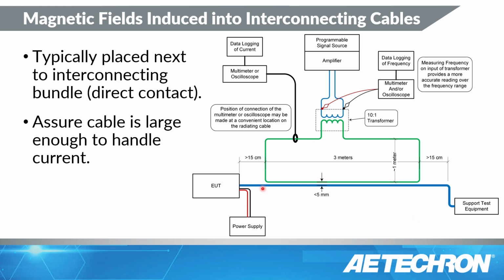The other thing is that you need to assure that you've got 15 centimeters between the end of the exposed cable and the EUT, also 15 centimeters between the end of the exposed cable and the support equipment. And the reason why we want to allow that is we don't want these fields that we're creating to couple into a connector at either end, because often these connectors will have wires that splay out, and those fields can get between the wires. That may be an unfair type test at that location. So make sure you're keeping that wire away from both connectors.